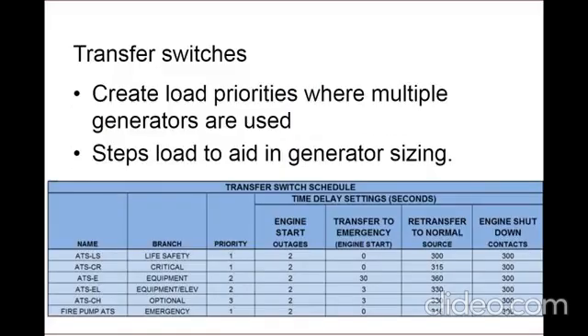So now we've figured out what belongs on each branch. Let's discuss how you create those branches within the system. As you recall from the diagram that we showed earlier, the branches are created by the use of transfer switches. Typically, you'll have a minimum of one per branch, but there are exceptions if your system design is less than 150 kVA. The key here is to work through your design and provide the appropriate number of switches. The larger your system is, the more switches you may desire. It creates added reliability as well as helps to step load the generator by applying your loads one at a time. Another thing to consider is load shedding.